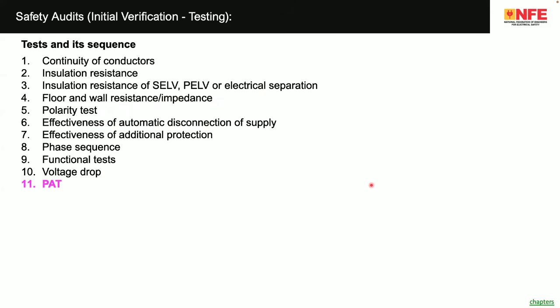Appliance test means just to confirm that the biomedical equipment is in good condition. Here, not only biomedical equipment, every electrical equipment you are using in the hospital, you are supposed to test. Example, if you are doing a PAT test on an air conditioner, even though the air conditioner is running 24 hours, if you make a PAT test probably once a year, you can very well find out the leakages and rectify them, so that the chance of fire from air conditioners can be avoided. Annually in India, almost 350 plus accidents happen due to fire from air conditioners alone.